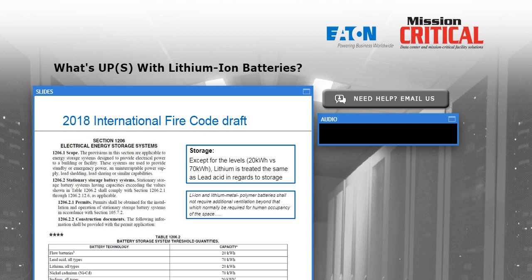For storage of the batteries, if you look on the right-hand side of the slide, except for the levels of energy, lithium is treated pretty much the same as lead-acid batteries in terms of safe storage. Below that, lithium-ion and lithium metal polymer batteries shall not require additional ventilation beyond that which is normally required for human occupancy of the space. So those are good news items.